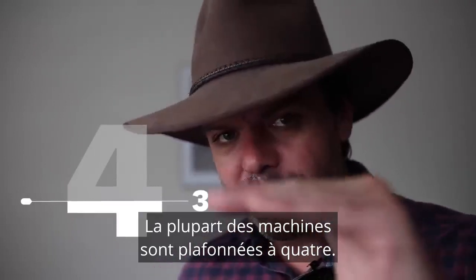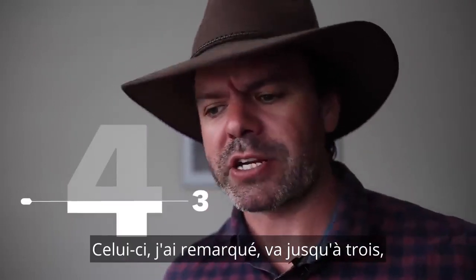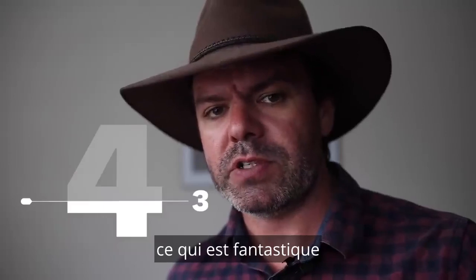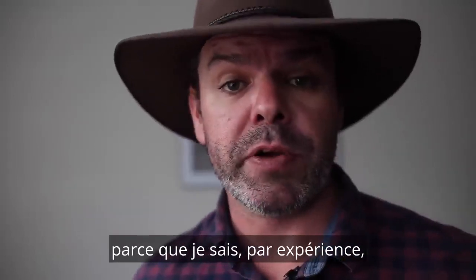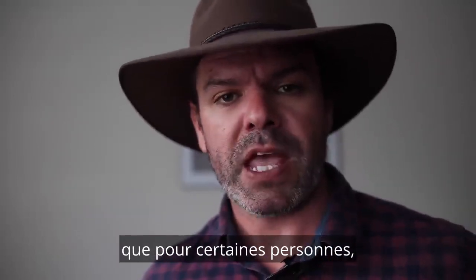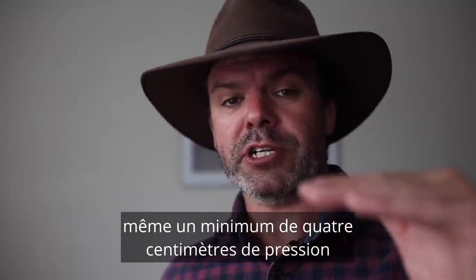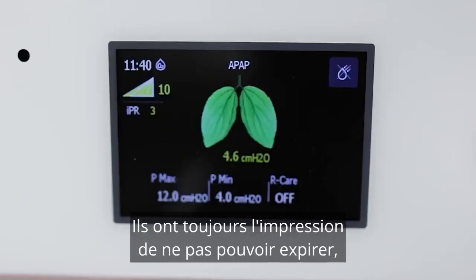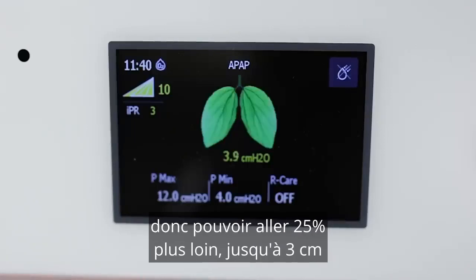Most machines are capped at 4 as the minimum. This one, I noticed, actually goes down to 3, which is fantastic because I know from experience that for some people, even a minimum of 4 centimeters of pressure is still too high. They still feel like they can't exhale.